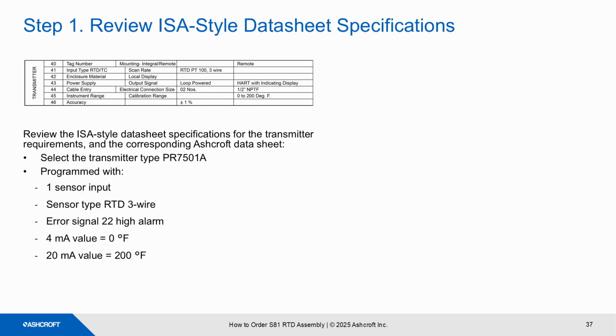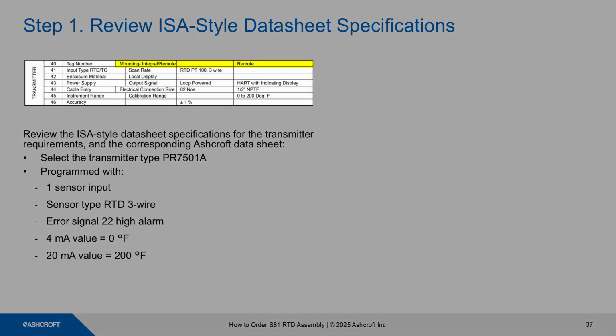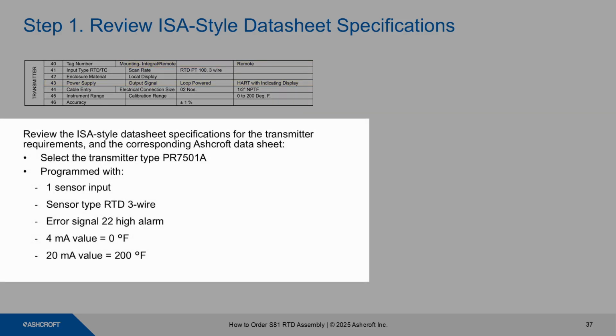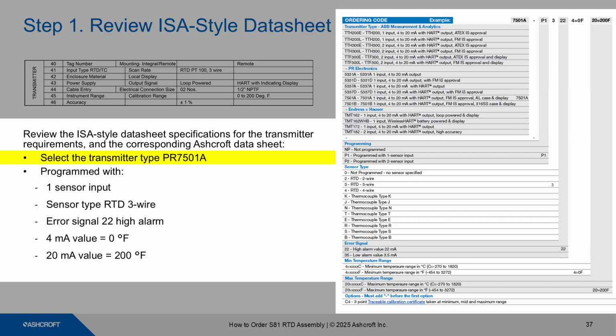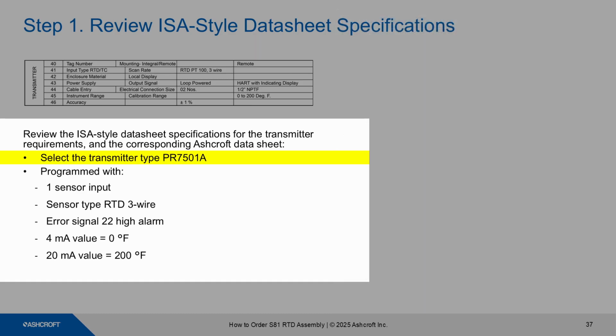So we're going to once again review the ISA style datasheet specifications, and we saw that it was a remote mount transmitter, HART, with indicating display. So for that, we're going to look at the Ashcroft transmitter datasheet, and we're going to select the transmitter, the PR7501A. It's going to be programmed with 1 sensor input, the sensor type being an RTD 3-wire. It's going to have an error signal of the 22 high alarm. The 4 milliamp value is going to be 0 degrees F, and the 20 milliamp value is going to be 200 degrees F.